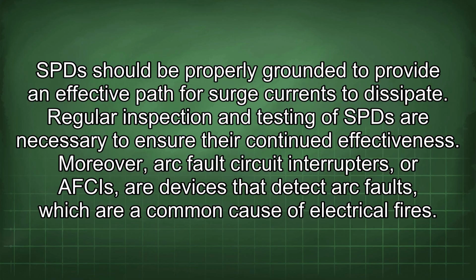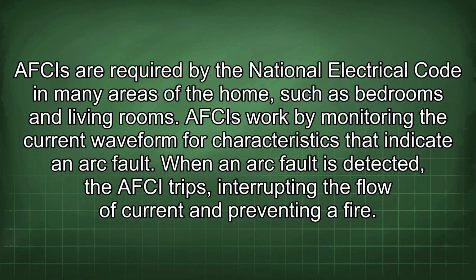Moreover, arc fault circuit interrupters, or AFCIs, are devices that detect arc faults, which are a common cause of electrical fires. AFCIs are required by the National Electrical Code in many areas of the home, such as bedrooms and living rooms. AFCIs work by monitoring the current waveform for characteristics that indicate an arc fault.